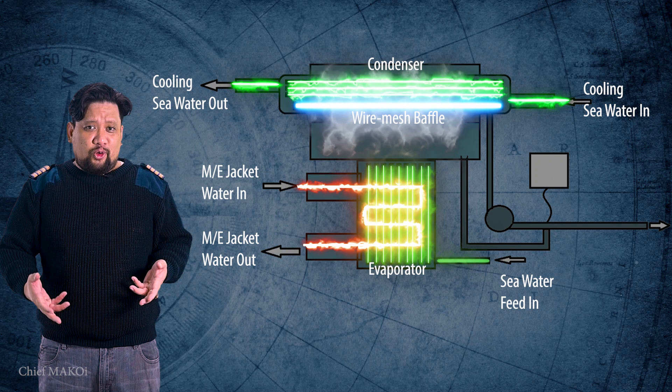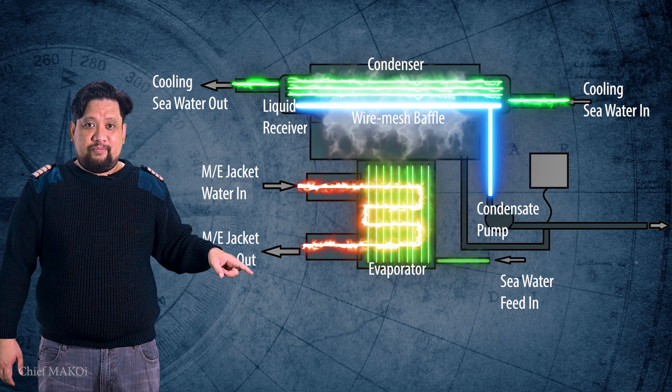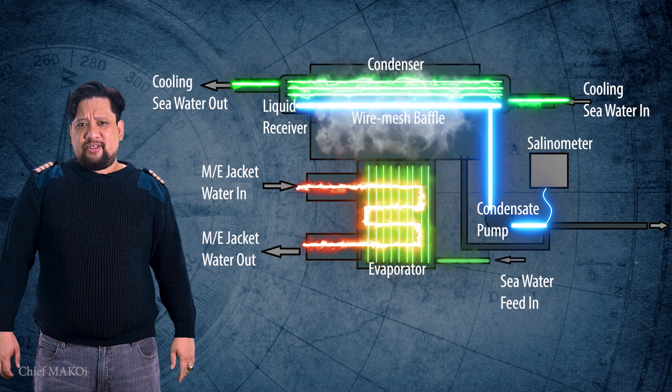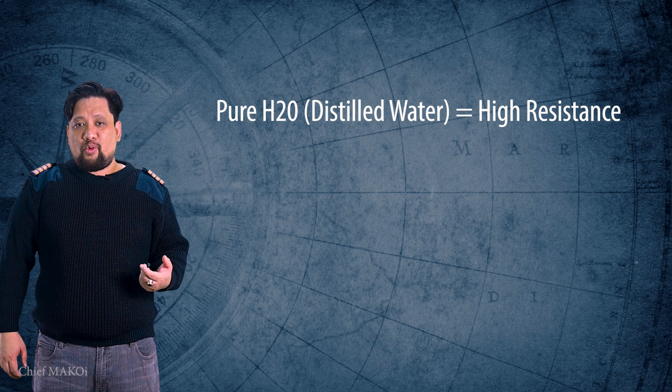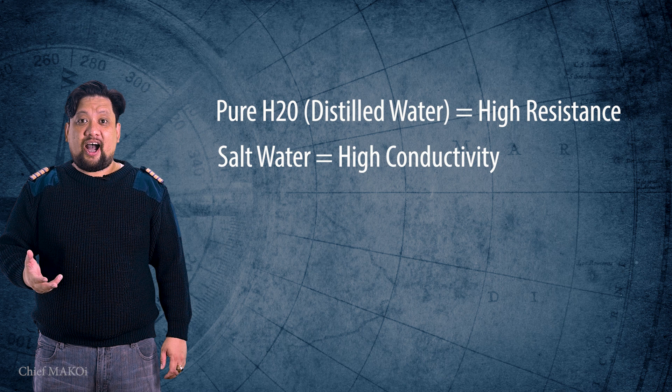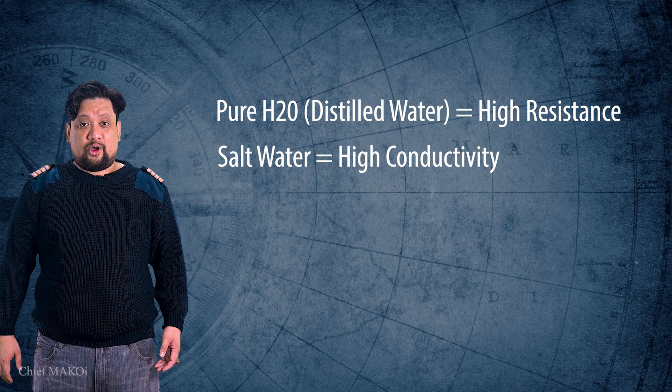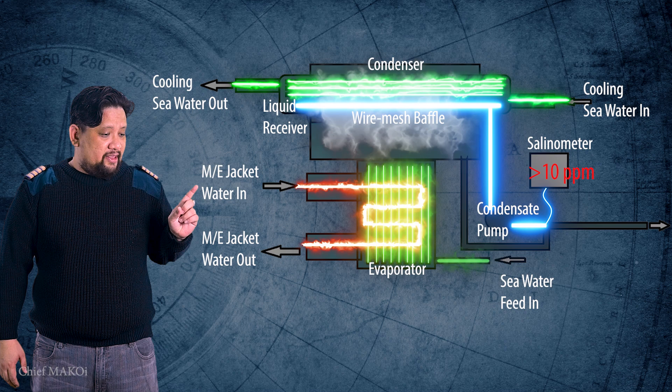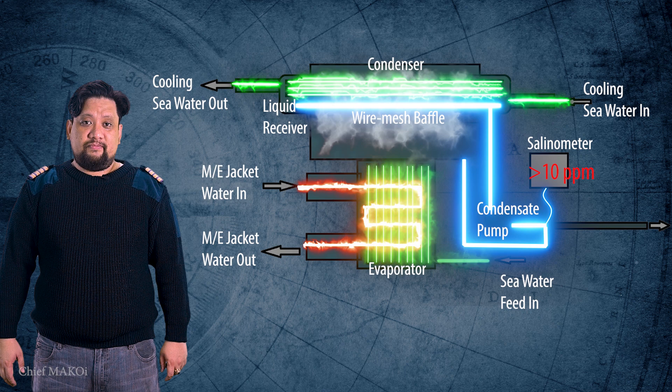The fresh water will be sampled and analyzed by the salinometer. The salinometer is a device which determines water purity in terms of absence of salt by measuring electrical conductivity. The concept is that pure water has a high resistance to electrical flow, as compared to salt water which has a high electrical conductivity. Therefore, the higher the current flow means more salt content. If the measured salinity is above 10 ppm, a magnetic valve activates and diverts the flow of fresh water back into the evaporator. If the water salinity is below 10 ppm, it is delivered into the ship's freshwater storage tanks.